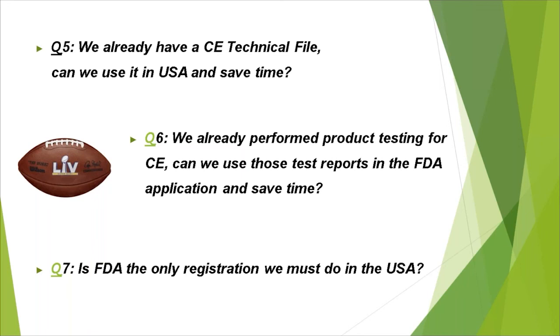As far as FDA being the only registration in the US, for many products, it's true. But there are some products where additional approvals are required. For example, antimicrobial coatings, even if they're simple, like silver or copper, the coating itself may need to be registered with the EPA.